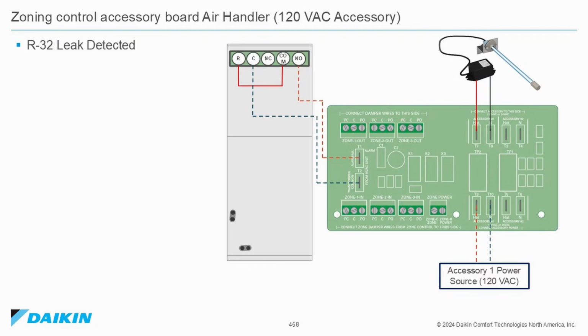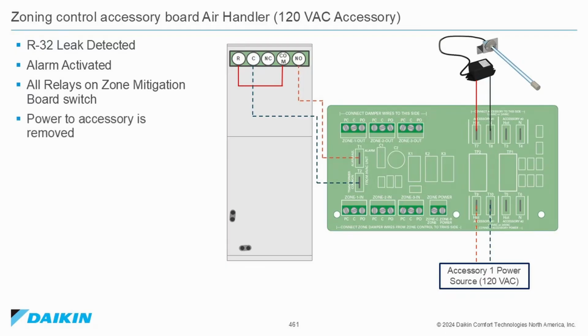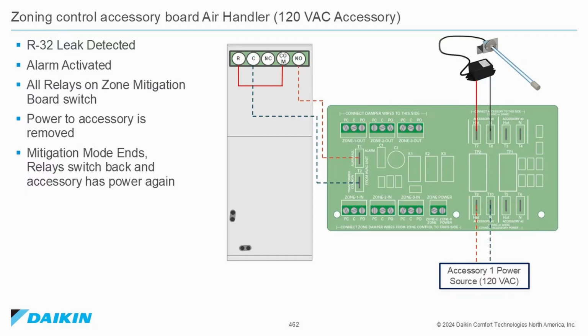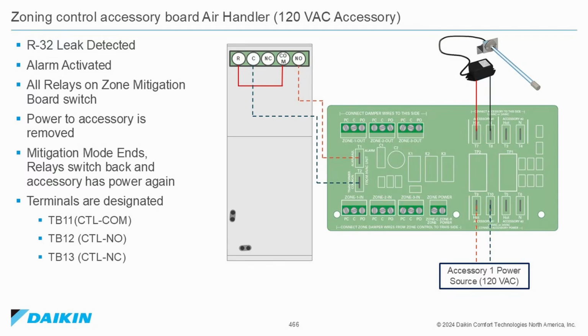R32 leak detected, alarm activated. All relays on zone mitigation board switch. Power to accessories is removed. Mitigation mode ends, relays switch back, and accessory has power again. Terminals are designated TB11, control common, TB12, control normally open, TB13, control normally closed. And the accessory 1 power source terminals is 120 volt AC.